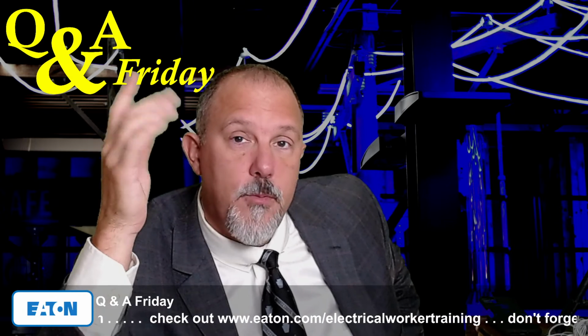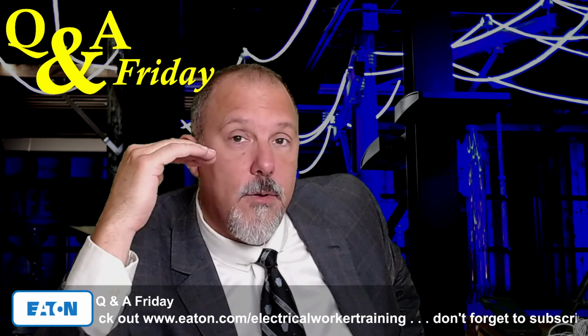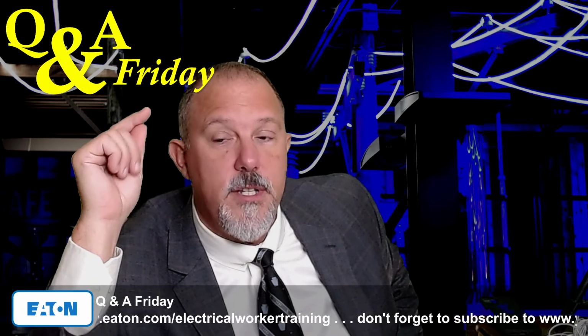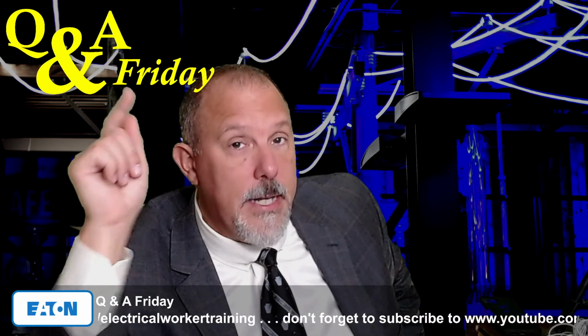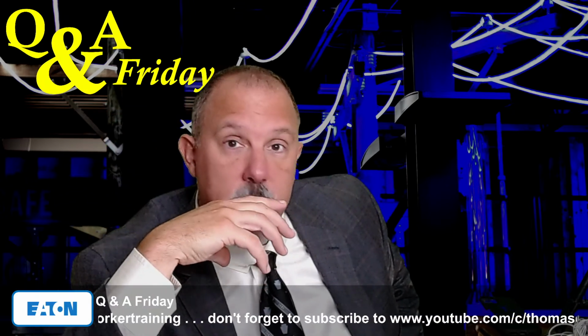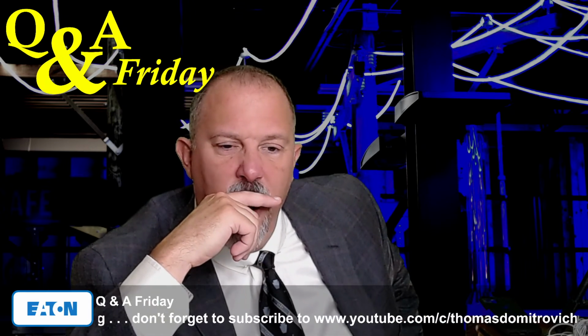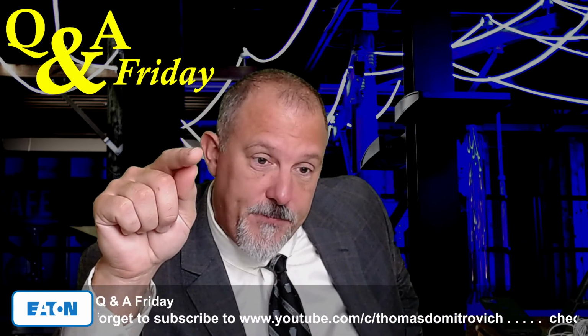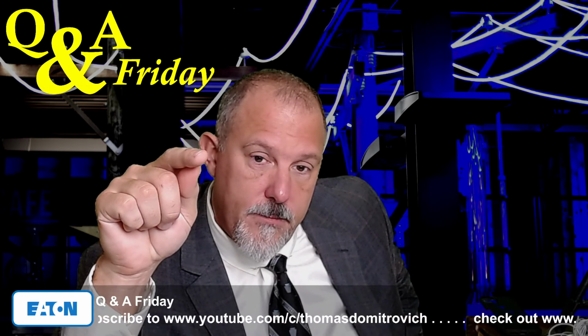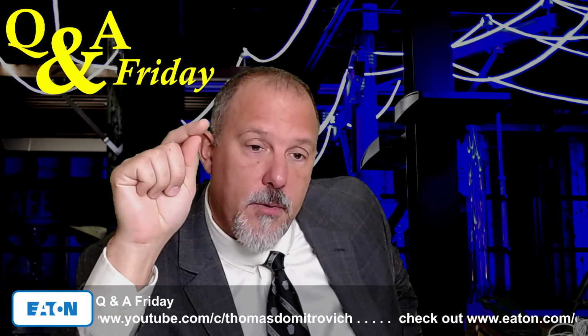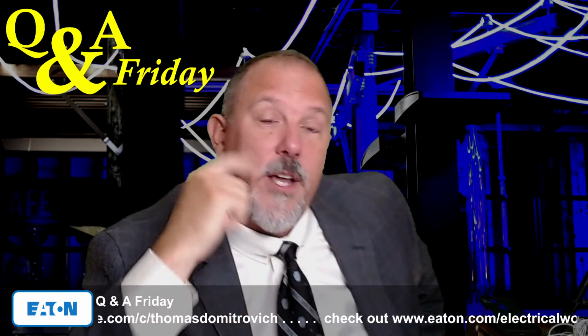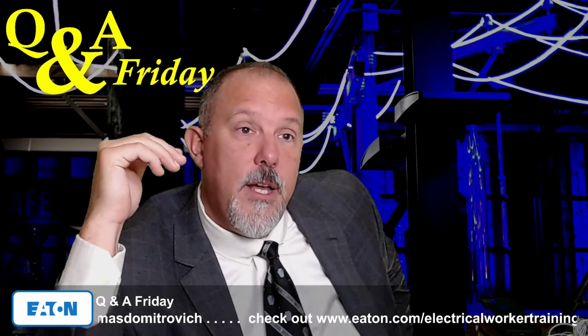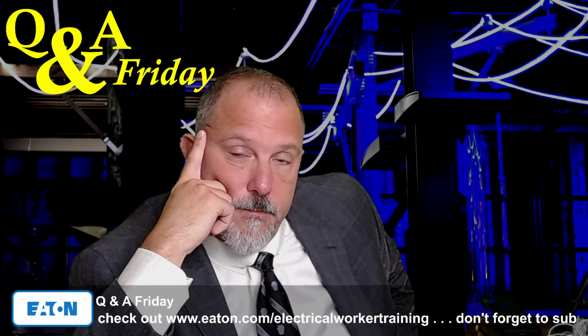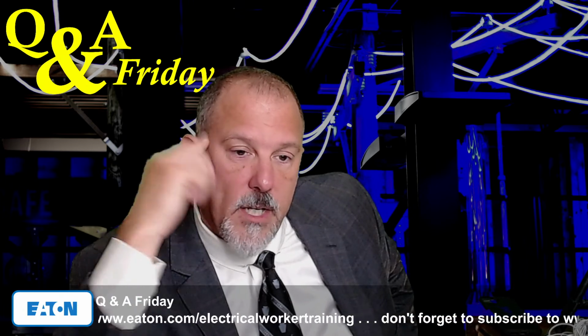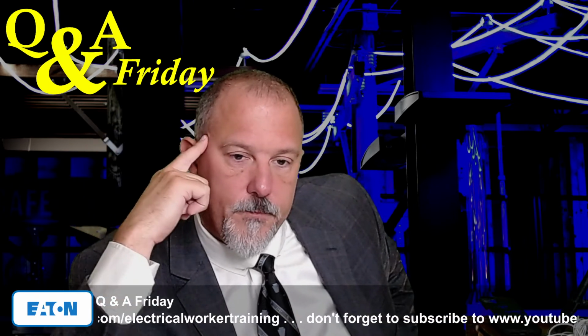But the relationship would be all around, where is your arcing current with regard to instantaneous? If it's already in the instantaneous region, then you don't need one of these other technologies. Technically, by the code, you don't need it, but there might be other reasons why you want it, because an arc reduction maintenance switch can look down further into the power distribution system. So hopefully that answers your question.